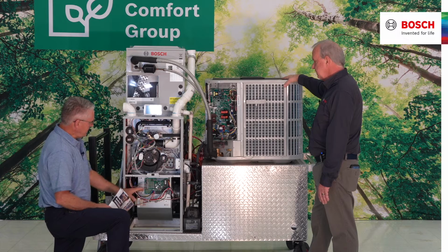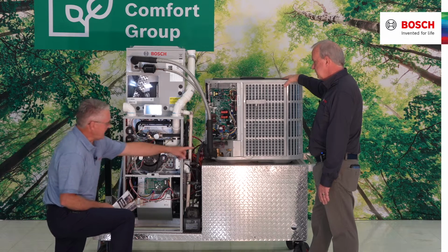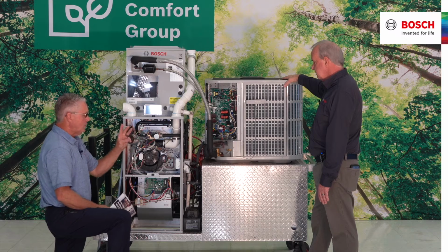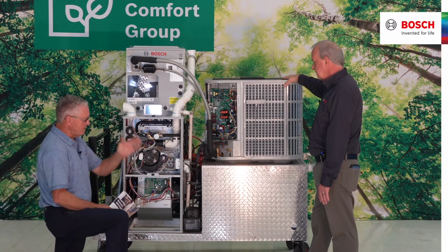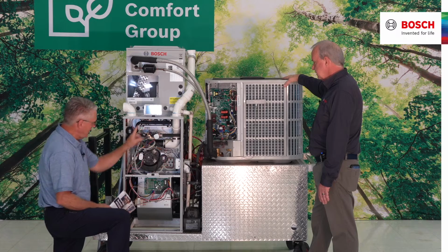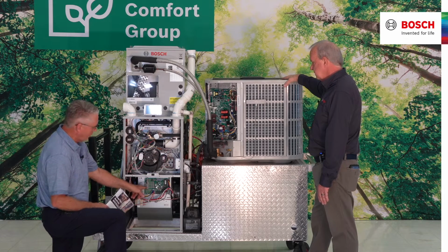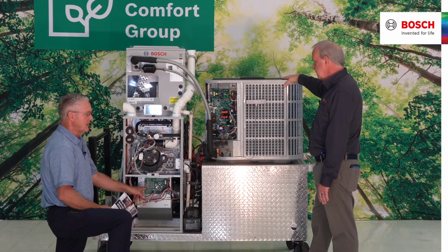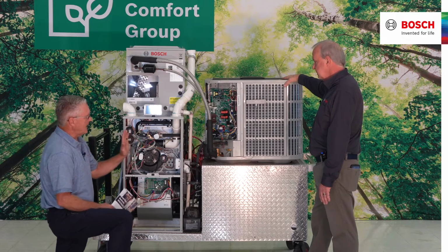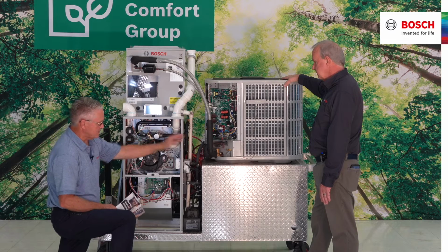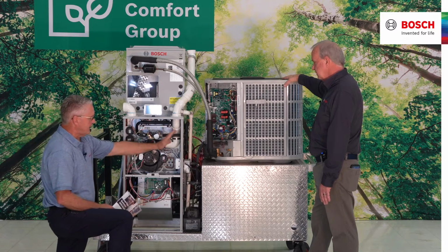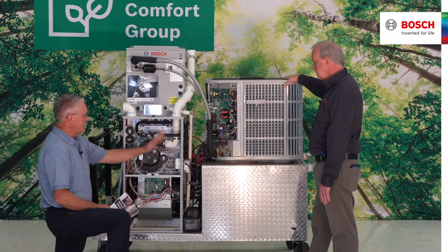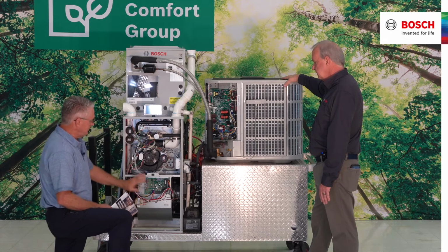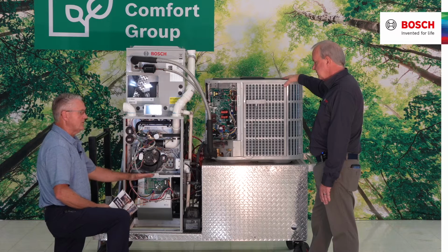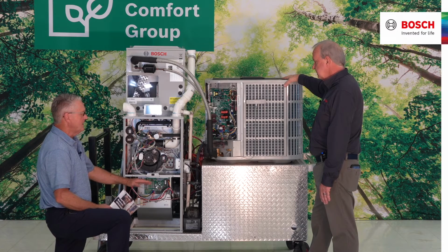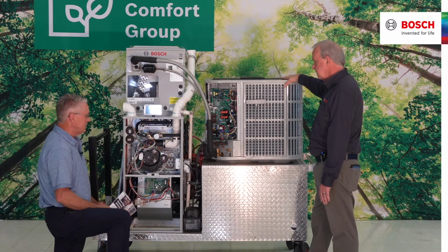One more thing about the control wires is that I have on my condensing unit a white wire, or what we would call a W wire. That W wire is going to come back and hook up to my board on the W1 side of the board. Meaning that when I go into a defrost mechanism or my system drops below 5 degrees outdoor ambient temperature, that particular system is going to fire up the low side, or the first stage, of my gas valve.